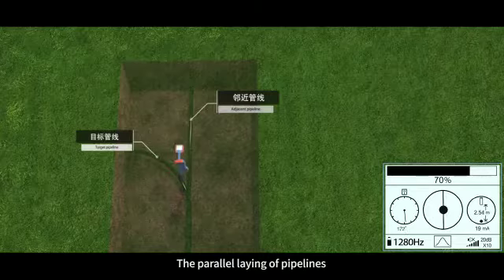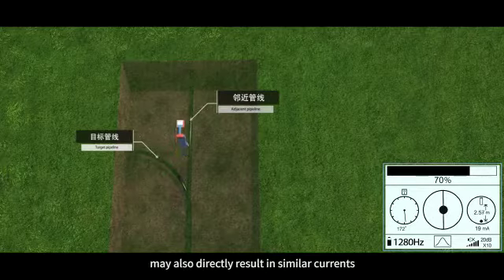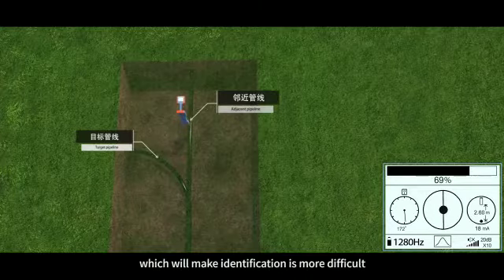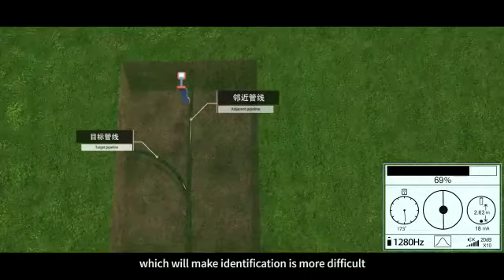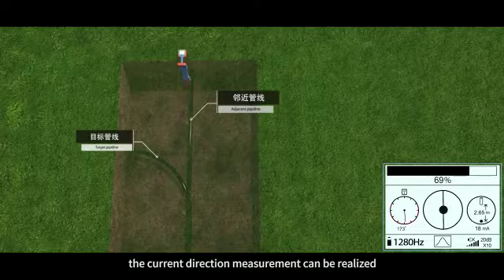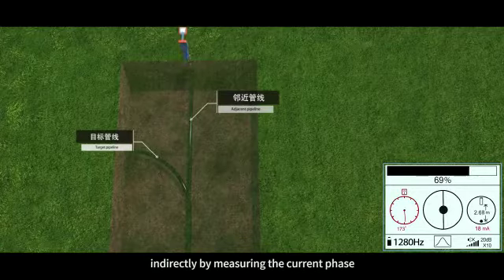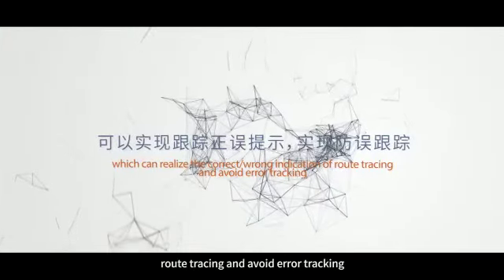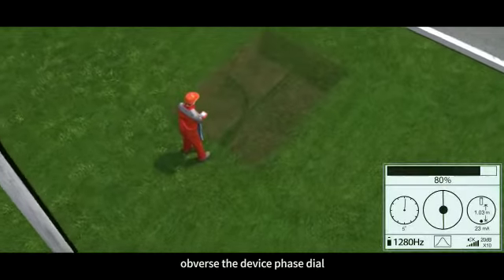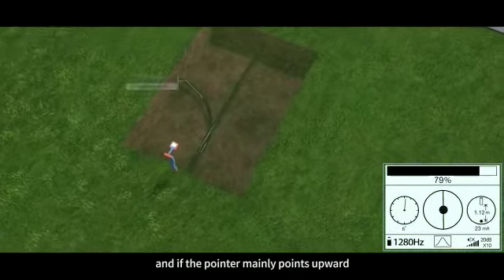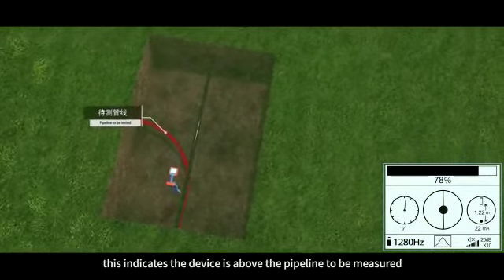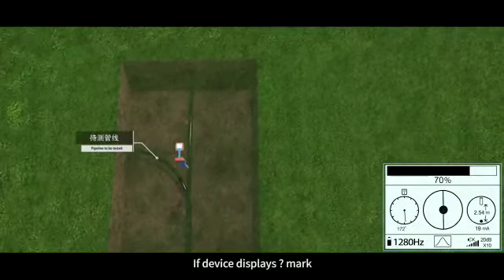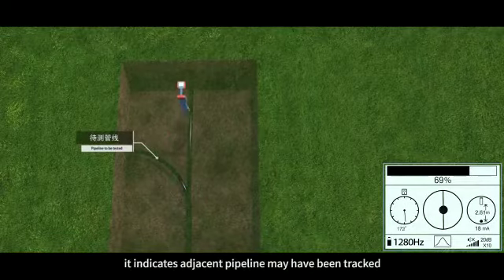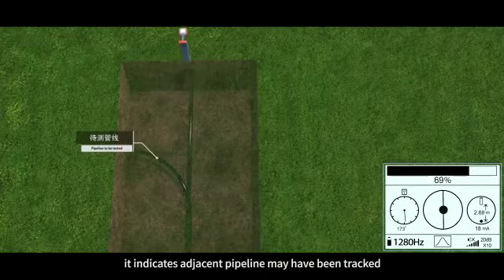The parallel laying of pipelines may also directly result in similar currents in adjacent pipelines, which will make identification more difficult. In this case, the current direction measurement can be realized indirectly by measuring the current phase, which can realize the correct or wrong indication of route tracing and avoid error tracking. During pipeline route tracing, observe the device phase dial. If the pointer points straight upward, this indicates the device is above the pipeline to be measured. If the device displays a question mark, it indicates an adjacent pipeline may have been tracked.